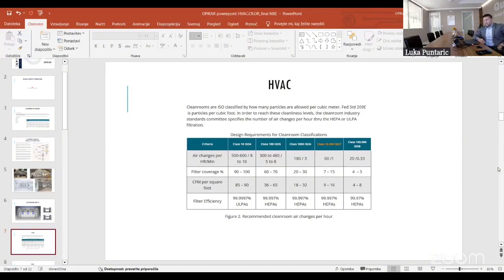What does this mean? Different clean areas have different cleanliness. 20 air change rate means how much air needs to be replaced every hour. So we calculate the volume of the room, always taking into account square meters multiplied by the height of the room. We get the cubic meters.